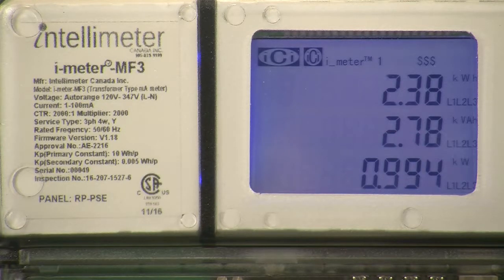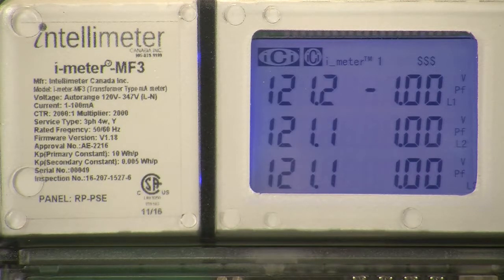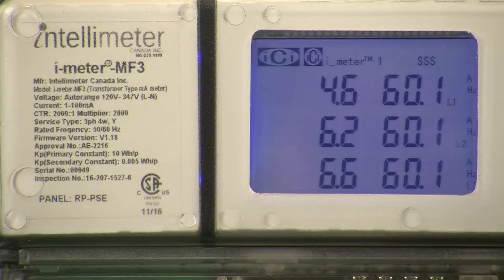Document your findings, and if needed, make corrections accordingly. All the same goes for line 2 for CT2 on phase B, and line 3 for CT3 on phase C.